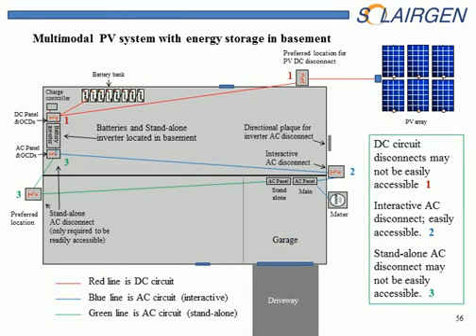In this drawing we have a multimodal PV system, and if they do have an energy storage system, it probably is a multimodal. Whether it's selling power back to the utility or not, it's probably a grid connected system with energy storage for backup. In this case it's in the basement. We have the batteries and the battery inverter, and everything's in the basement. The PV array is on the ground outside, which is pretty typical of systems with energy storage. So if this is the case, all you have to do is find that disconnect and you've stopped the DC power from coming in from the PV array.